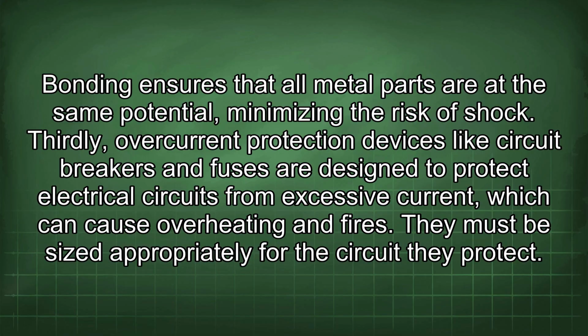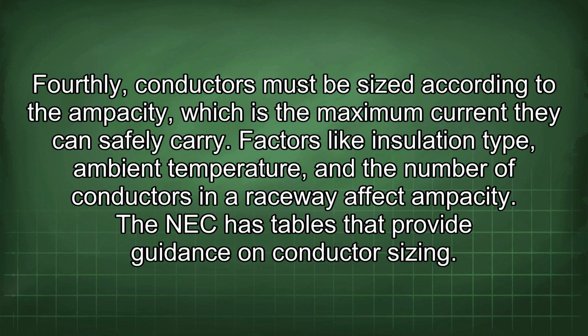Thirdly, overcurrent protection devices like circuit breakers and fuses are designed to protect electrical circuits from excessive current, which can cause overheating and fires. They must be sized appropriately for the circuit they protect. Fourthly, conductors must be sized according to the ampacity, which is the maximum current they can safely carry. Factors like insulation type, ambient temperature, and the number of conductors in a raceway affect ampacity. The NEC has tables that provide guidance on conductor sizing.